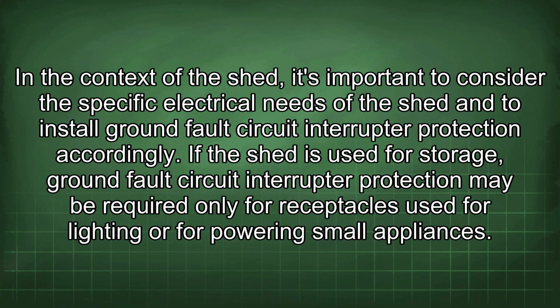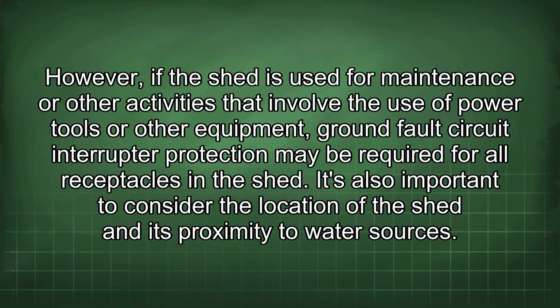In the context of the shed, it's important to consider the specific electrical needs of the shed and to install ground fault circuit interrupter protection accordingly. If the shed is used for storage, protection may be required only for receptacles used for lighting or for powering small appliances. However, if the shed is used for maintenance or other activities that involve the use of power tools or other equipment, protection may be required for all receptacles in the shed.